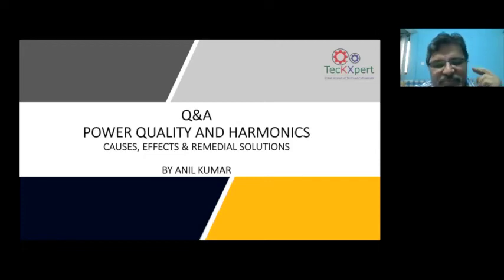Thank you for the knowledge on the harmonic study. Then I have one question, sir. I have a 350 kVA APFC panel with a detuned reactor. Particularly on the 100 kVA reactor, twice the white phase lead only burned out. So what is the reason? Is there any harmonics? There is no loose connection, nothing has happened, but the same phase lead burns out like a welding. This lead is fully cut. So what is the reason, sir?